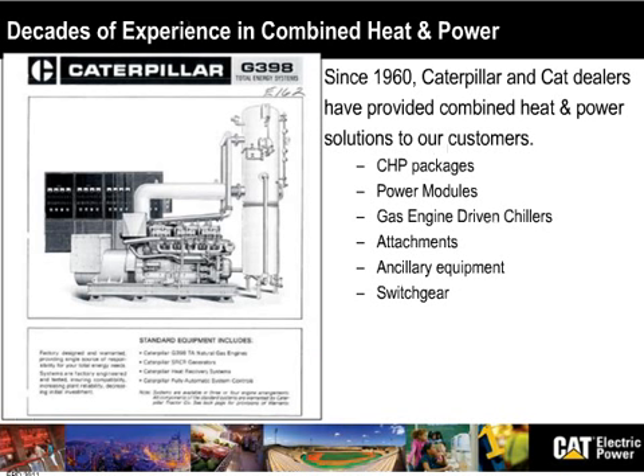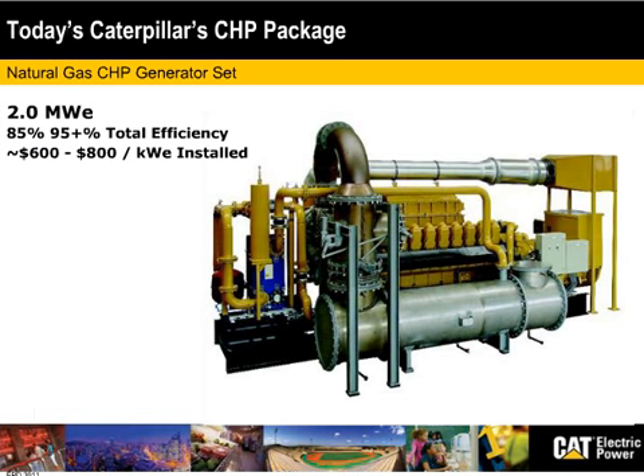Is CHP a new concept? No, it's not. If you look at this slide, Caterpillar has been delivering CHP system globally since 1960, and I brought up this old brochure of ours that showed our old CHP system in the past. Today, the CHP system will look this way. This one is a 2 megawatt CHP recovery. You see in the front the water recovery from the jacket water and the aftercoolers, and here on the side of the genset you see the exhaust gas heat recovery.